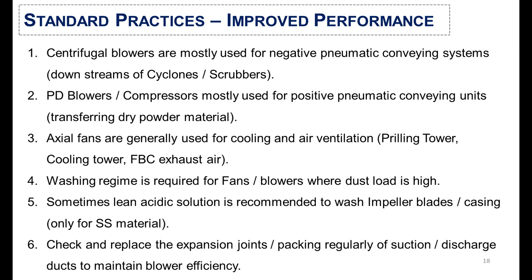Here are some standard practices for improved fan and blower performance. First, centrifugal blowers are mostly used for negative pneumatic conveying systems, such as at the downstream of cyclones or scrubbers. Second, positive displacement blowers are mostly used for positive pneumatic conveying units to transfer dry powder material from one location to another. Third, axial fans are generally used for cooling and air ventilation systems such as in prilling towers, cooling towers, fluidized bed coolers, and exhaust air systems.